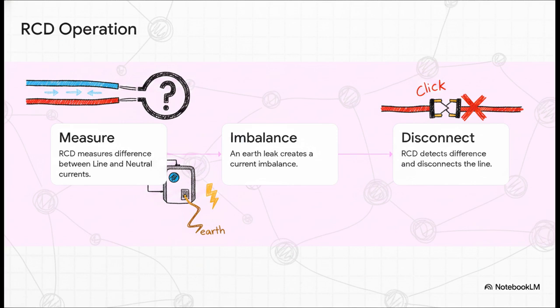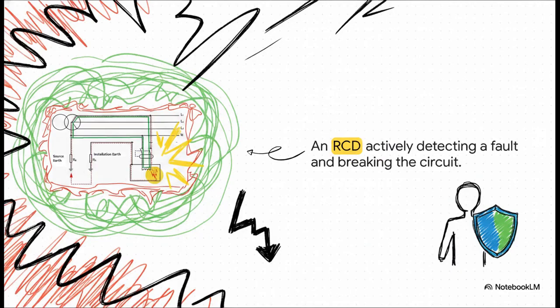Here's how it works. Step 1. The RCD constantly monitors the current going out on the line and coming back on the neutral. Step 2. If power leaks to an earth casing, it creates a tiny imbalance. Step 3. The RCD detects that discrepancy in a fraction of a second and instantly severs the circuit. Look closely, right at the moment a fault happens. The normal path of electricity suddenly leaks out down into the installation earth. The literal microsecond that happens, the returning neutral current drops slightly below the outgoing live current. The RCD immediately senses that the scale is unbalanced and just throws the breaker open. It acts so fast that it saves your life long before a lethal shock can even be delivered.